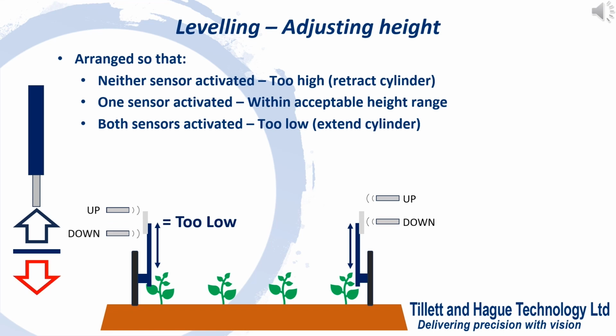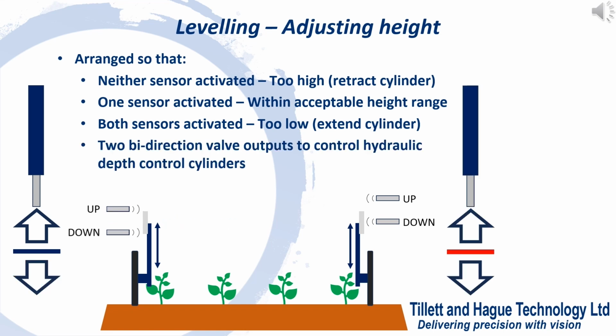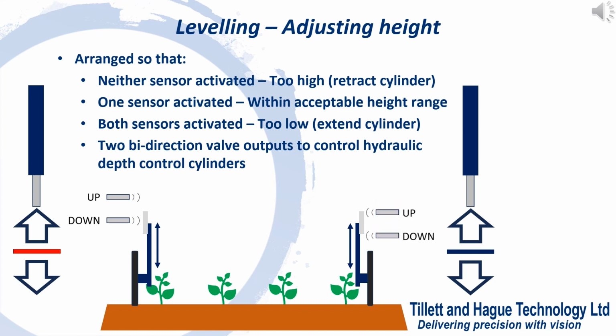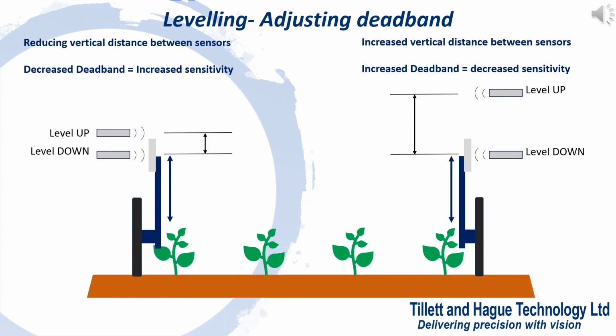Bidirectional valve outputs are activated on the basis of the position sensors to bring the frame into alignment. Adjustment is therefore done purely by the mechanical positioning of the sensors relative to the mechanism they are sensing. The further the 2 sensors are apart, the larger the deadband in level adjustment.